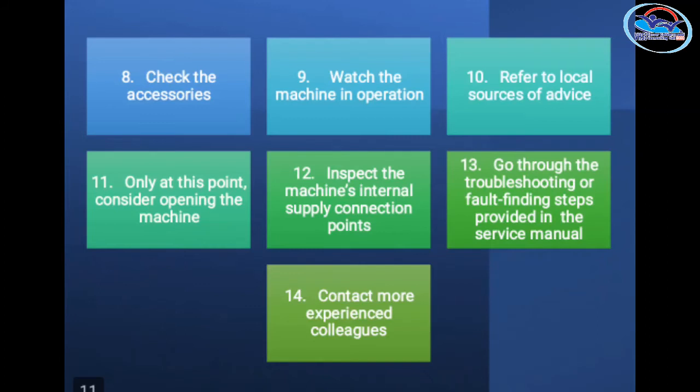There is a service manual provided by the equipment company. The service manual contains the manufacturer's guidance and troubleshooting steps. If the medical equipment technician is unable to resolve the issue, they should contact more experienced colleagues in the next step. These are good practice steps in maintenance and fault-finding.